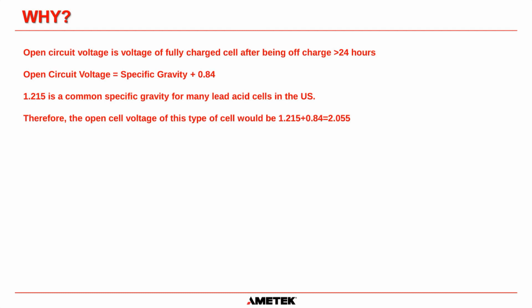And in truth, if you had a cell that had been off charge for 24 hours and the open circuit voltage you measured was less than 2.055, then you can start to assume that there may be something wrong with that battery. Obviously, you would have to check the specific gravity of the electrolyte with a hydrometer to make sure that it is 1.215 before you add that 0.84 on. But if they don't match, then there is something wrong with that battery.